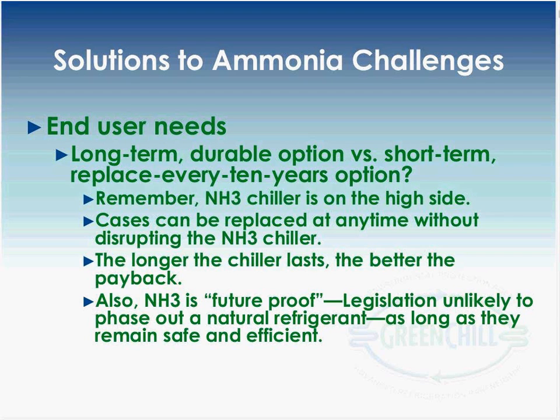Ammonia is on the high side, so you've got this secondary system inside the store. You can touch the sales floor all you want, you don't have to touch the ammonia system. So really, the longer your ammonia system lasts, the better the payback, and it's future-proof because it's unlikely any legislation would phase out a natural refrigerant as long as it continues to be safe and efficient.